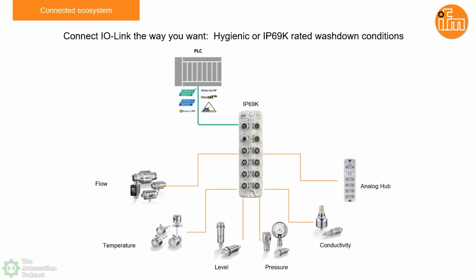So you don't have to take one or two analog devices back to the PLC directly. You can still keep it within this architecture by collecting these 4 to 20 milliamp signals, because although IOLink is used primarily for sensor intelligence communication, we have a larger bandwidth of data being transmitted, so we can take the analog values, collect them in this hub, and bring them back. In this case, we can bring back 8 channels of 4 to 20 milliamp or 0 to 10 volt signals to the PLC with just one device. That's, from my point of view, a very cost-effective way of bringing analog back.